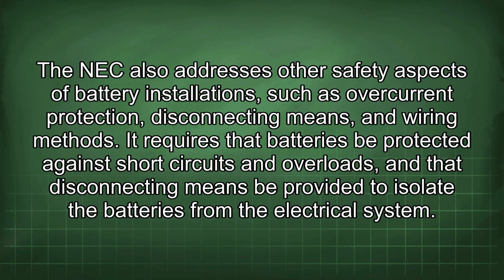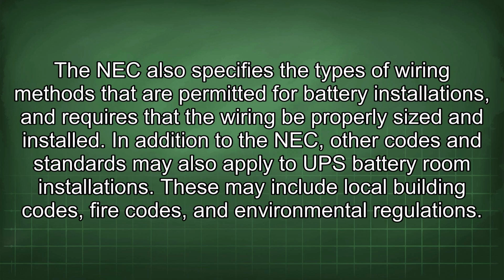The NEC also addresses other safety aspects of battery installations, such as overcurrent protection, disconnecting means, and wiring methods. It requires that batteries be protected against short circuits and overloads, and that disconnecting means be provided to isolate the batteries from the electrical system. The NEC also specifies the types of wiring methods that are permitted for battery installations, and requires that the wiring be properly sized and installed.